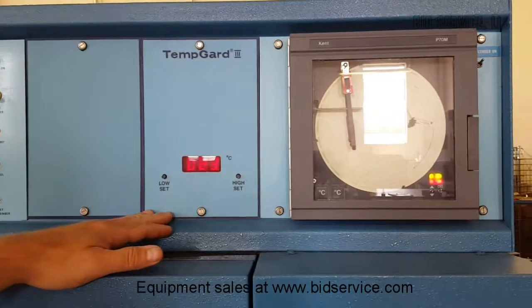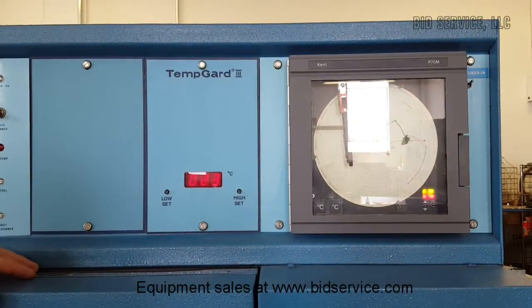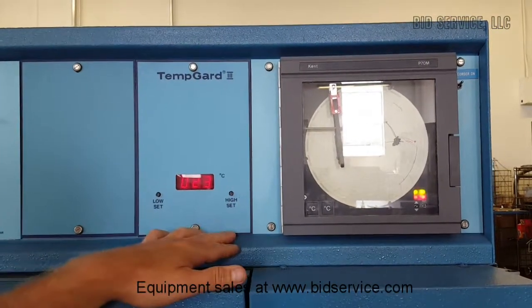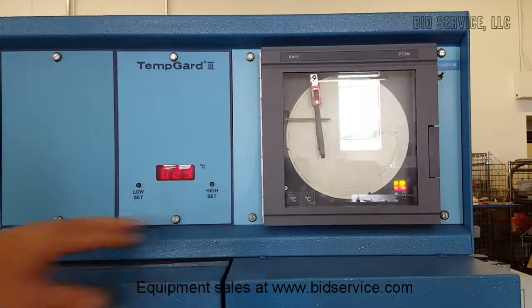This is the TempGard III controller for the cold side chamber, which also has a heater in it, so this one can be used both ways with the low and high set points. And then you have the optional chart recorder for monitoring your temperatures in the chamber.